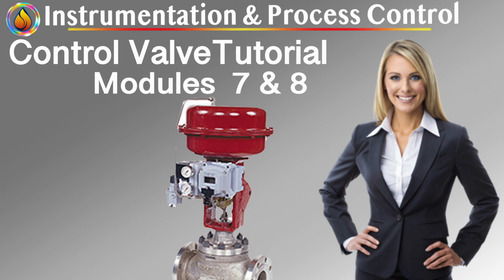Sensitivity. Sensitivity defines the smallest change in input signal that produces a measurable change in valve position. Limiting factors: positioner resolution, actuator compliance, signal noise, mechanical friction. Low sensitivity means the controller cannot finely modulate flow, integral action becomes aggressive, and noise-driven oscillations increase. High sensitivity without stability, however, leads to chatter. Control quality lies in the balance.